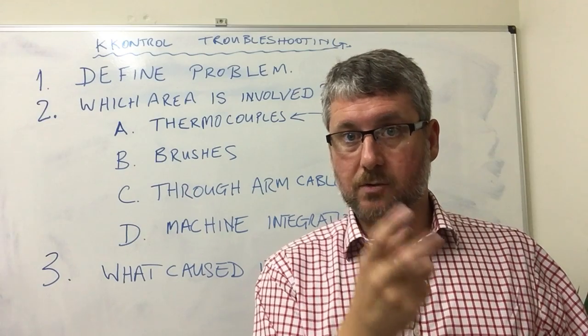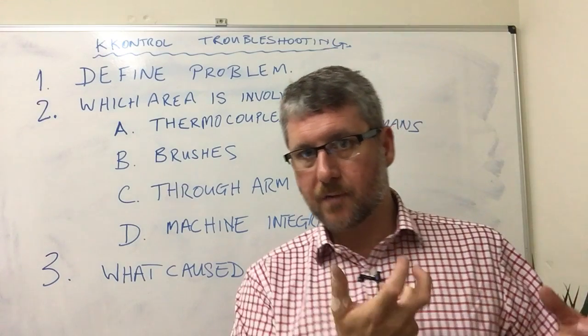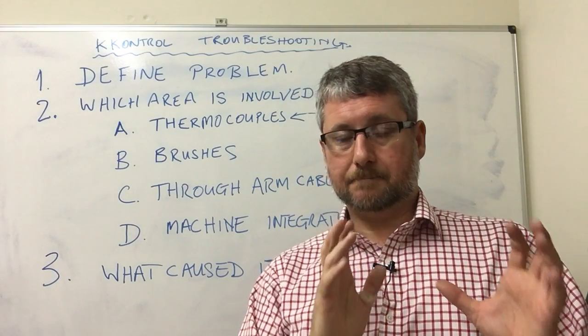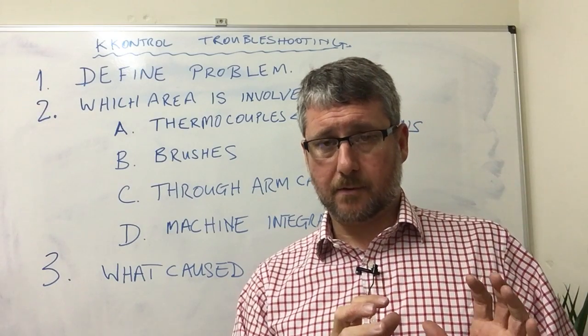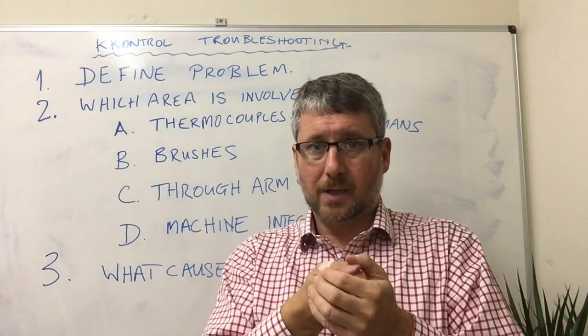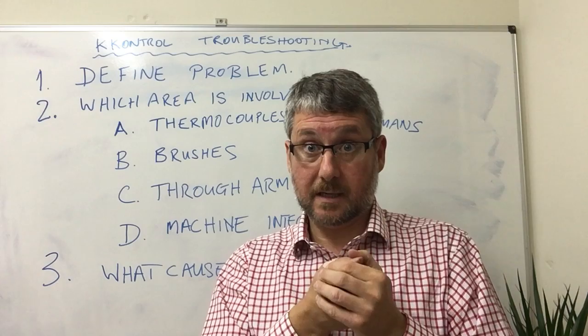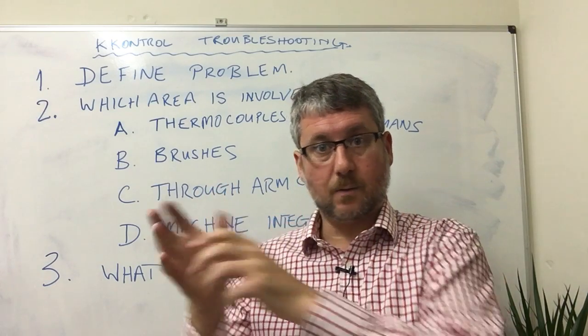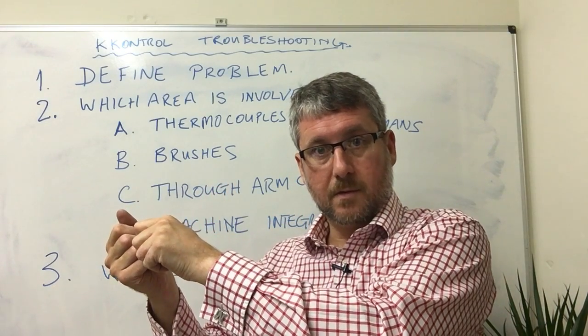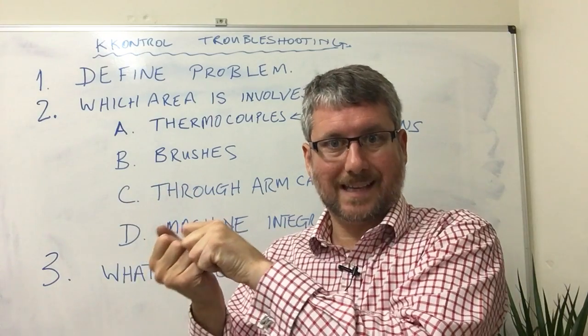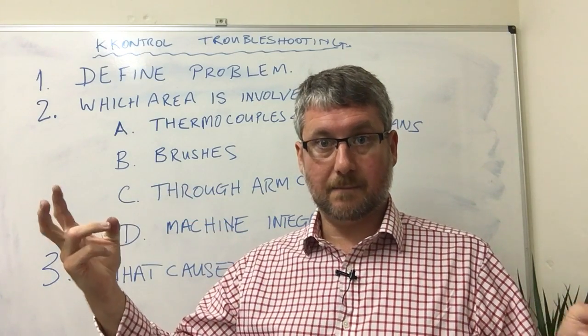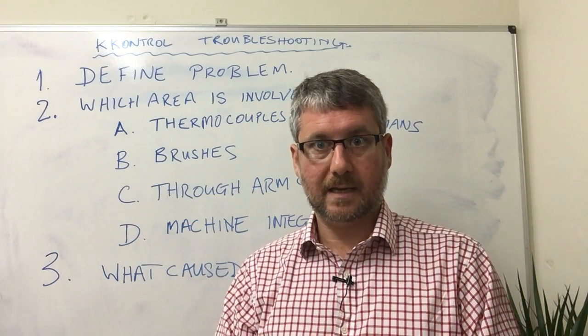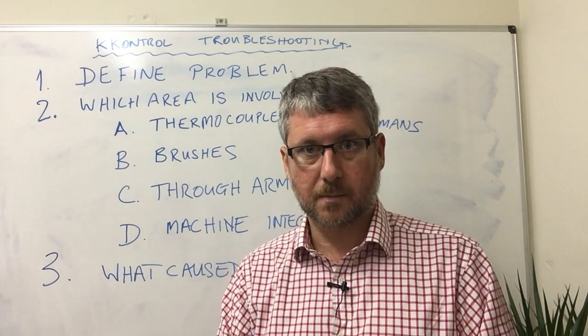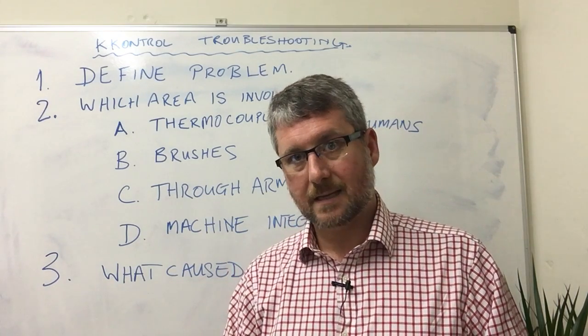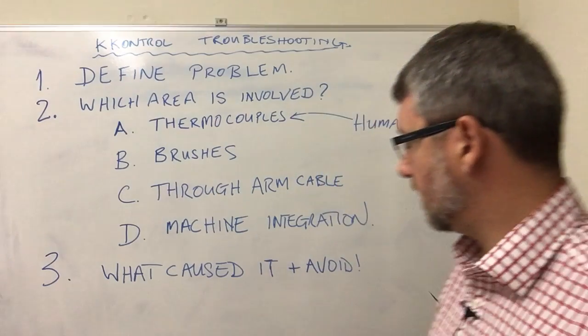It's important also that you tell your operators, when they're removing the thermocouple from the slip ring, not to pull it with the cable. Yeah, that's very important. And likewise, removing the probe from the mold, don't pull it with the cable. Use the handles on each end to pull off. Okay, and if you don't have handles on your thermocouples, we can supply those. That's simple.